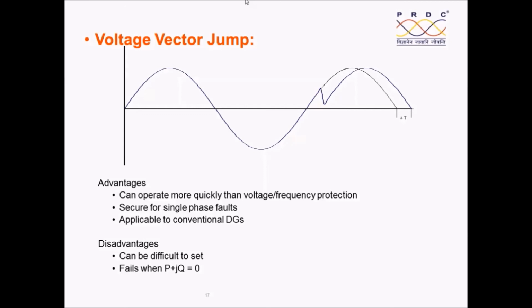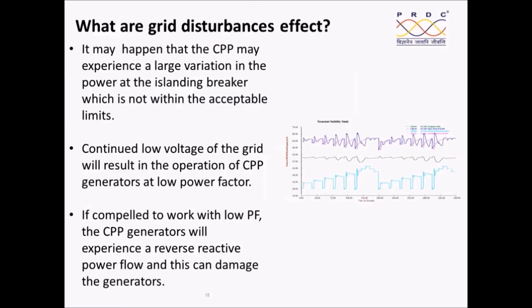But whenever there is a major grid loss, or a major fluctuation in the power, meaning you are either exporting or importing power, and at that time the grid is lost, then the voltage vector jump happens and you can ensure that this relay is going to operate.